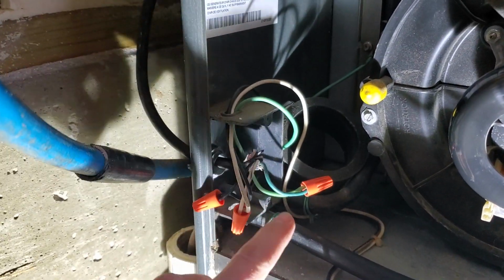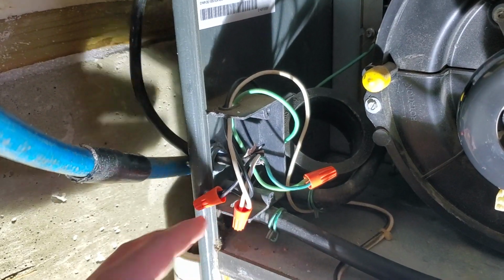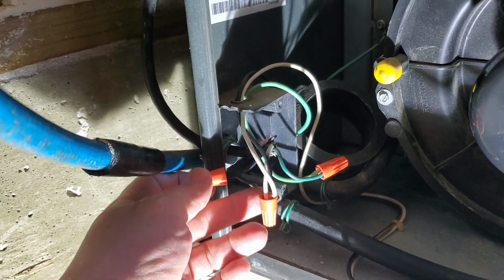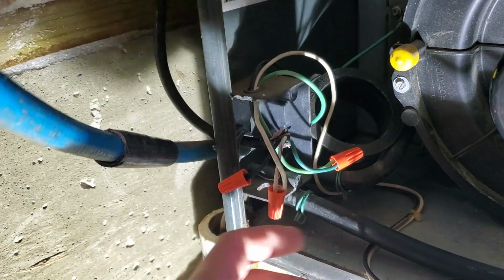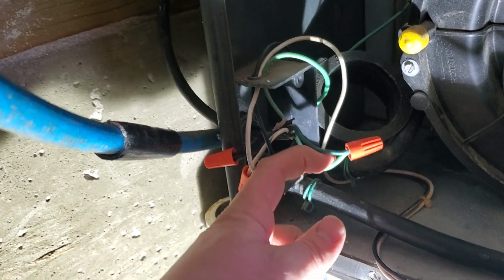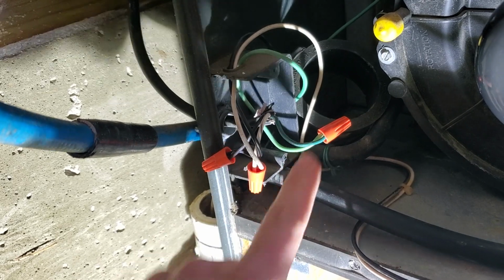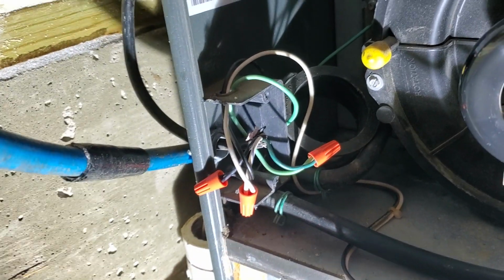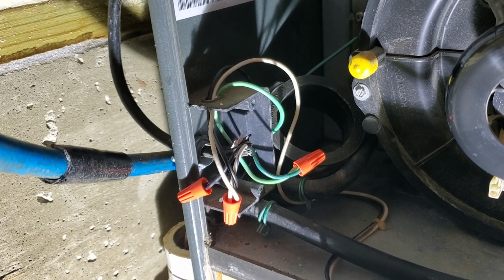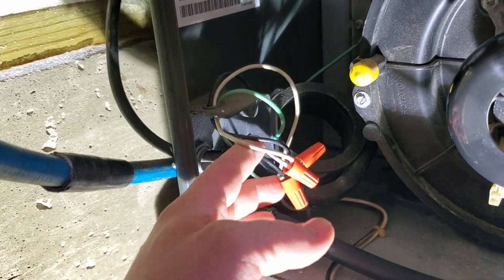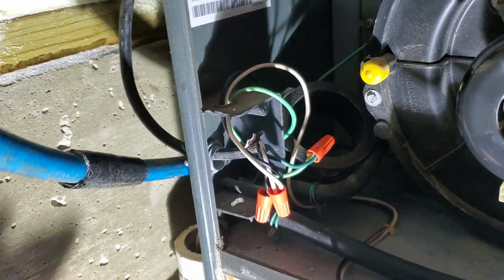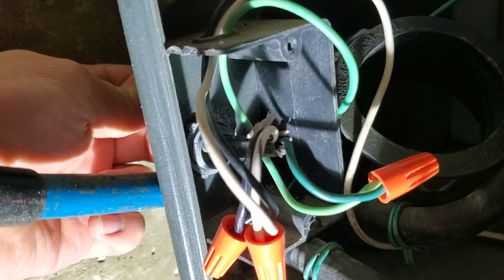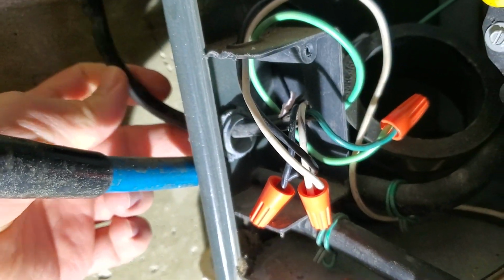So it's very, very important that you do not reverse the polarity. You need your hot to be hot and your neutral to be neutral. And then it's also very important that you have a good ground. If you don't have a good ground, the furnace will not operate with most modern furnaces. So make sure you have good connections through and through for your 110 volts. And we have that clamped securely going through the sidewall of the furnace.